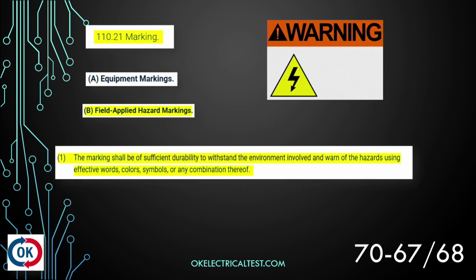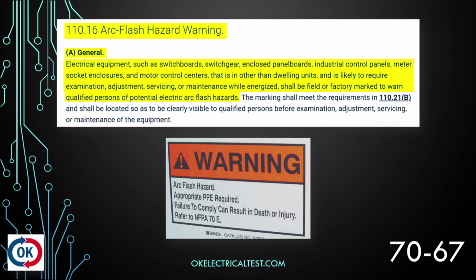Let's move to 110.21 marking. And we're going to skip letter A, equipment markings, and jump down to letter B, field applied hazard markings. Number 1 says the markings shall be of sufficient durability to withstand the environment involved and warn of the hazards using effective words, colors, symbols, or any combination thereof. And so ANSI Z535 is actually where we find the regulations for the symbols and the colors and things like that. Here this is a warning sign. It's got an orange colored background to it, right? That's going to be something that's dictated by that. Same thing that we saw here on the previous sign, right?